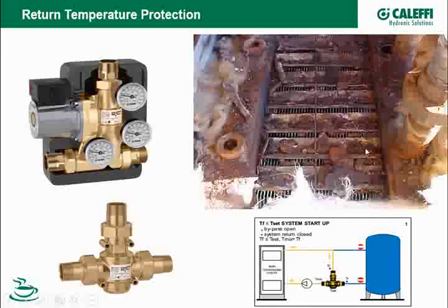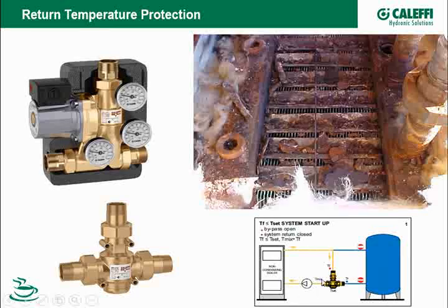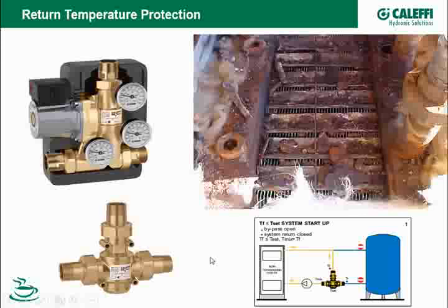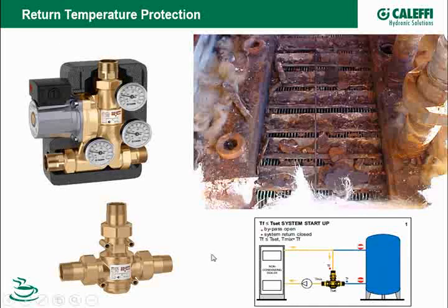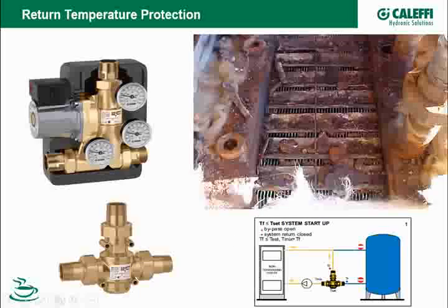If this type of boiler was connected to a low mass, low water content system, this type of protection wasn't as critical because they could get up to temperature quickly. I'm talking about a system maybe with thin tube, copper tube baseboard heat. It doesn't hold a lot of water. It's got a very low mass to it, so it can heat up quickly. So this boiler can get out of condensing mode within the first 10 minutes that it fires up.